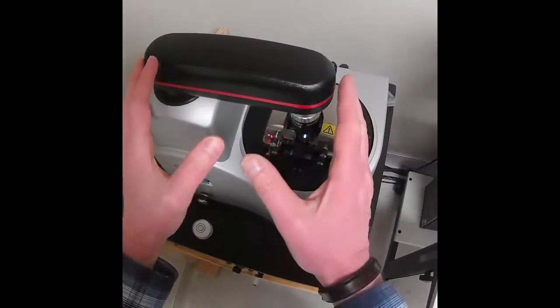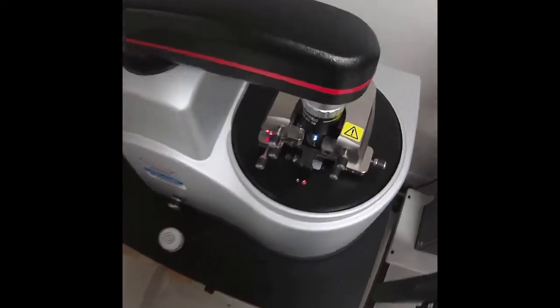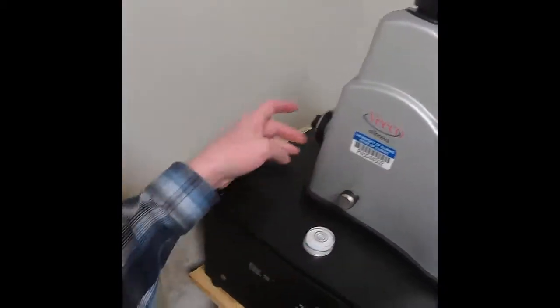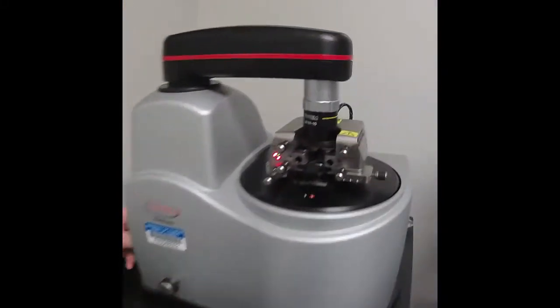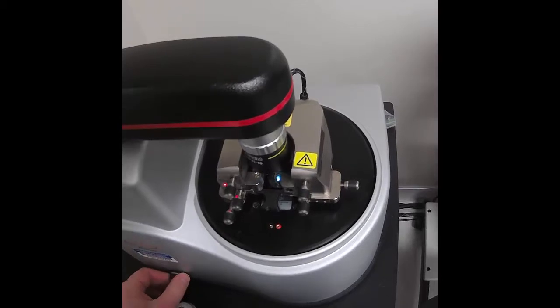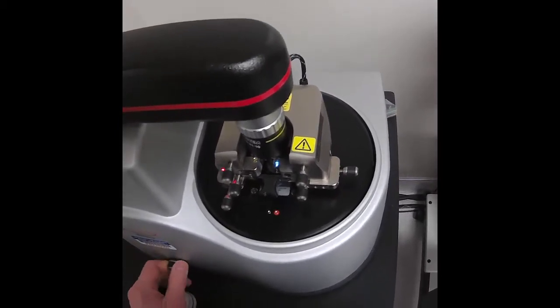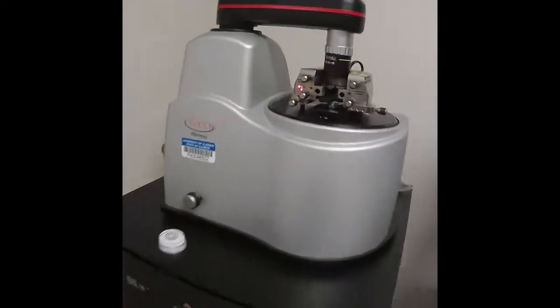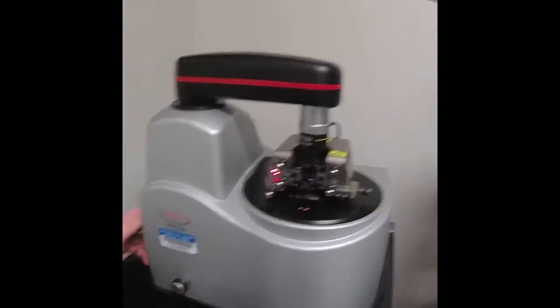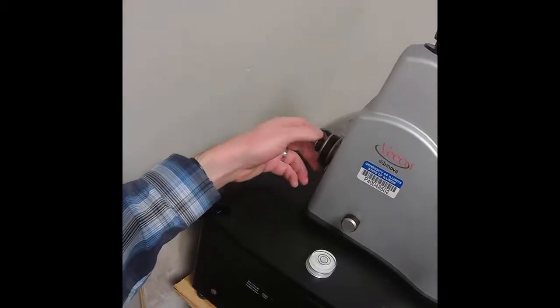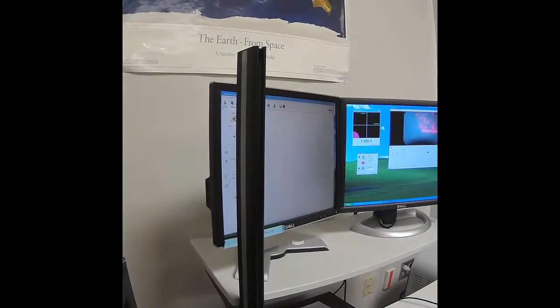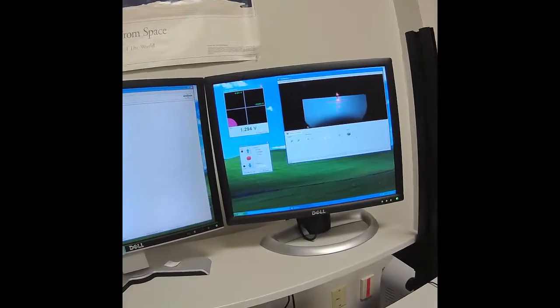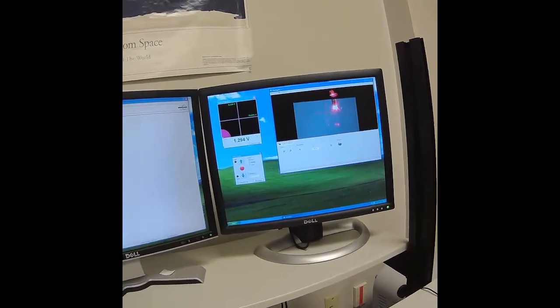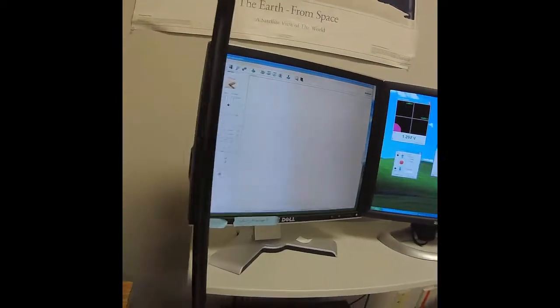Now we need to move the optical boom camera so it's looking at where the probe is, and to do that we use these 2 knobs here. And so if we move these knobs, we should see the light from the camera moving. Okay, so now we can focus on the probe and check the alignment. These are the focus knobs for the optical camera. The larger one's the coarse, the smaller one's the fine. Move those gently, they are breakable. Another video shows you how to align the probe. When you're done with the alignment procedure, it should look something like this, where the spot is being reflected off the end of the cantilever.